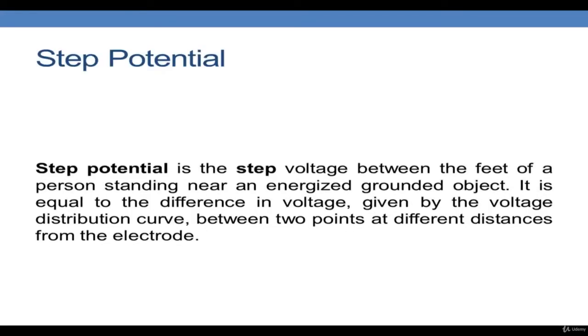And next we will discuss what the step potential is. Step potential is the step voltage between the feet of a person standing near an energized ground object. It is equal to the difference in voltage given by the voltage distribution curve between the 2 points at different distances from the electrode. So during a fault, a large voltage will be induced in all the other conductors in the substation. If we are about to touch these conductors, we will get a shock because the fault current causes induced voltage on this equipment. Then there will be a ground potential rise, and because our 2 feet are at 2 points, there will be a resistance between them or a potential difference between them. So this causes the step potential.